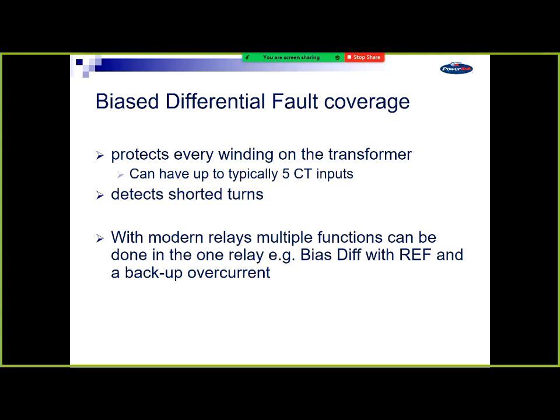Yeah, and you can do multiple functions in these relays. So in all of these relays, we do our circuit breaker fail. So we go and trip the circuit breaker, and we start CB fail internal in the relay as well.